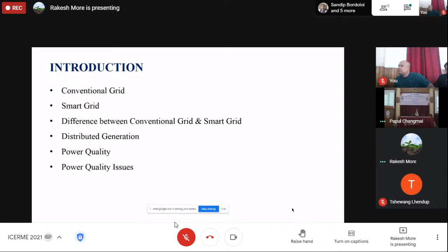The various power quality issues in the voltage waveform are as follows. First is the voltage sag. As per IEEE standard 1159, a voltage sag means a decrease in the system voltage level to between 0.1 and 0.9 times the normal RMS system voltage. The cause of voltage sag is mainly faults happening on the transmission line. Also, when we connect very heavy or non-linear loads in the system, meaning the starting of a heavy load, it affects the voltage profile, due to which voltage sag occurs.